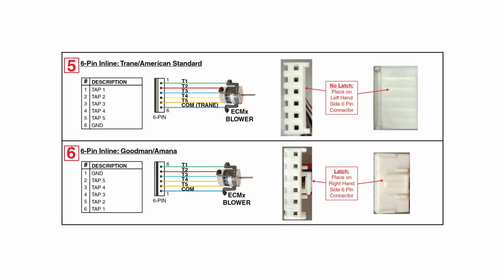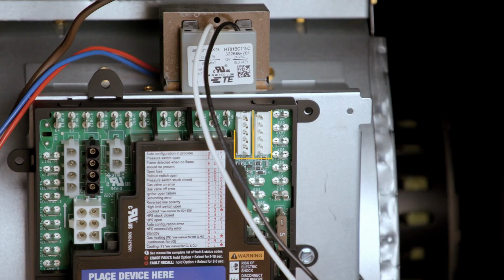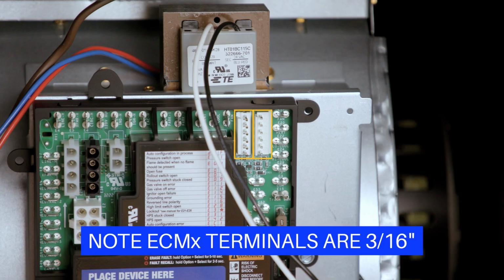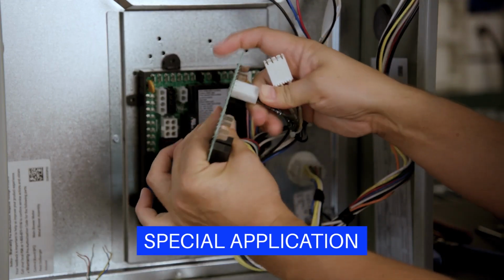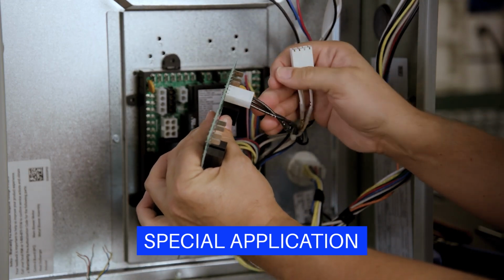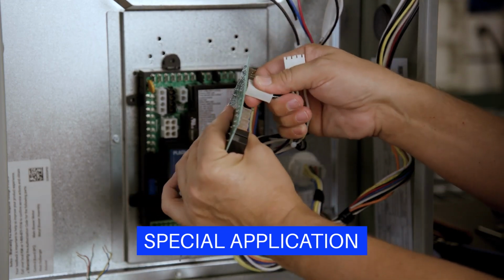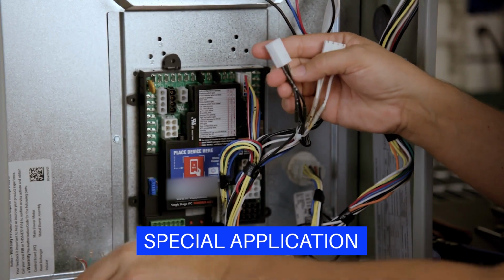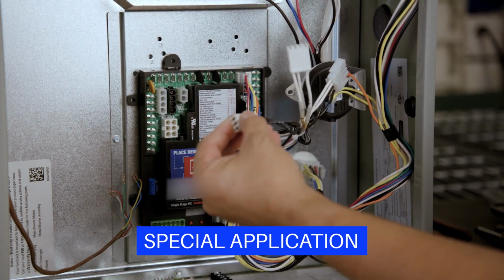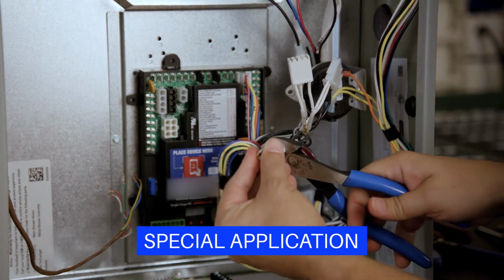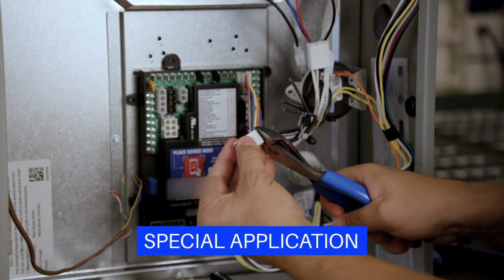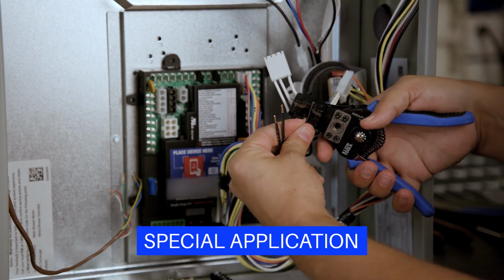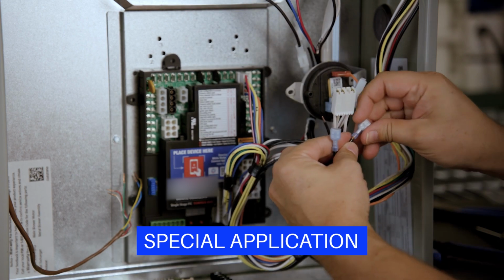For 6-pin ECM-X applications, identify the correct connector on the control and plug in the ECM-X motor harness. For ECM-X spade terminal applications, plug the motor wires on the matching terminals. Take note of special case applications in the installation instructions. Some OEM wiring uses a plastic connector housing to group together 120-volt power and neutral terminals. For these applications, cut the wires near the housing and install the supplied 1/4-inch Quick Connect spade connectors.